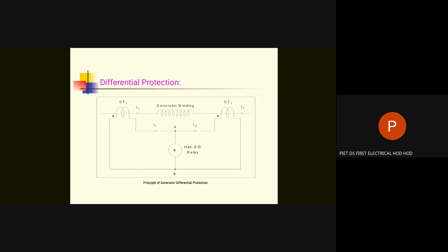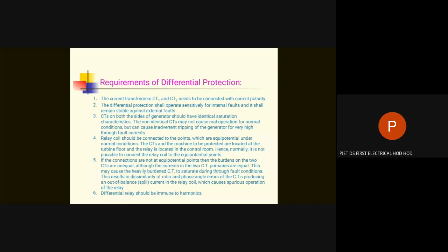And to avoid this, once again you have to connect the stabilizing resistance in series with the relay coil. This is a very important requirement. So that's how the differential protective system, which has been discussed in a simple way, goes on becoming complicated.